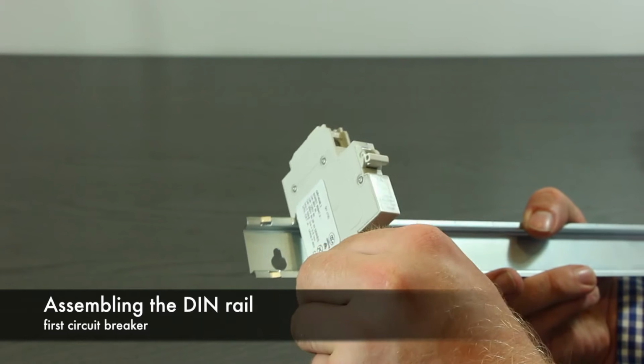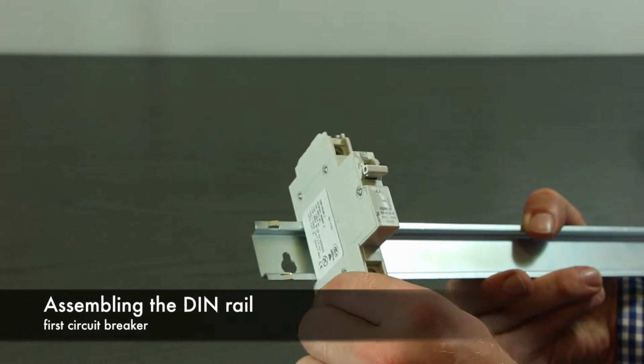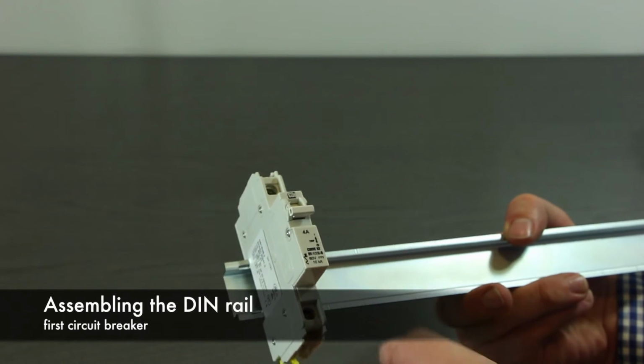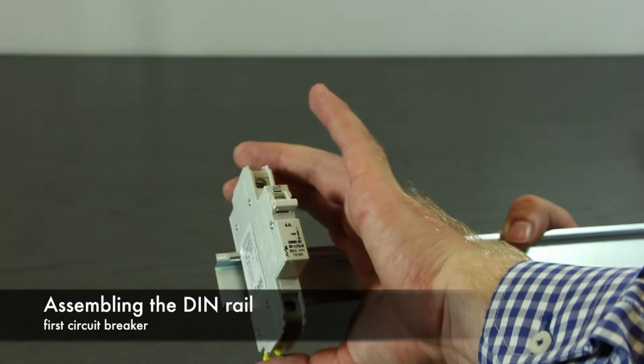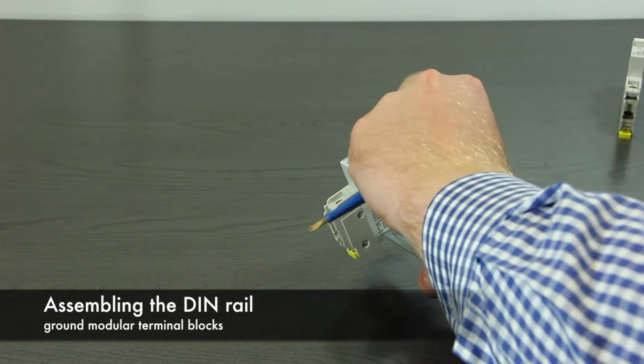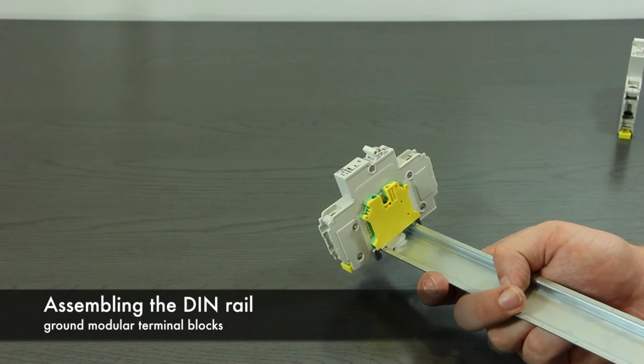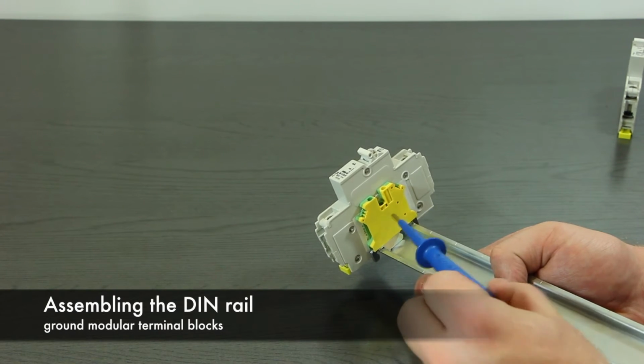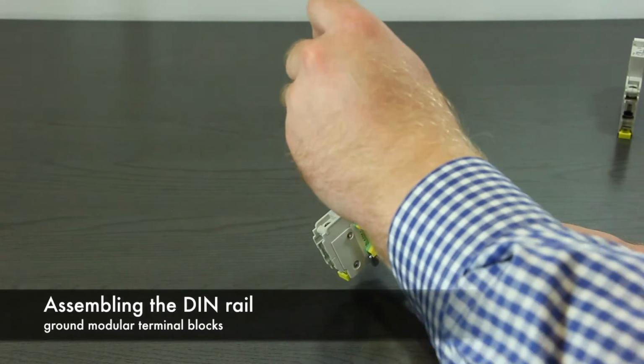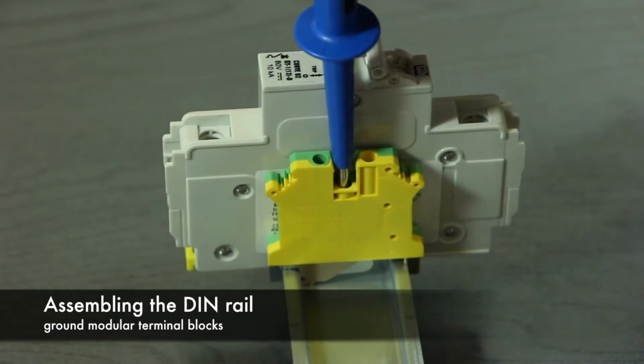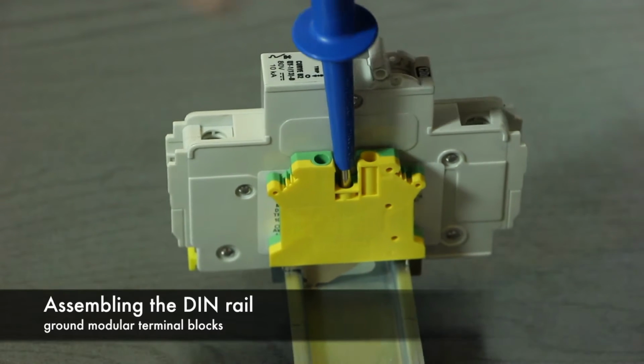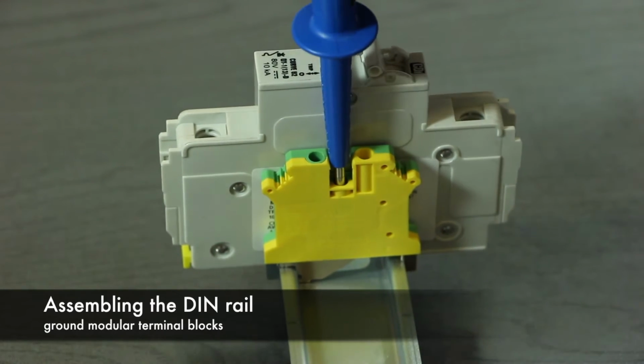Clamp the first 4A circuit breaker at the left end of the DIN rail, sitting closely to the notches. Secure it with the yellow locking slide. Place 1 terminal block on the right of the circuit breaker without clearance. The terminal block connects to the DIN rail via a metal hook. Tighten the screw of the terminal block to lock the hook to the DIN rail and check the connection for tightness.